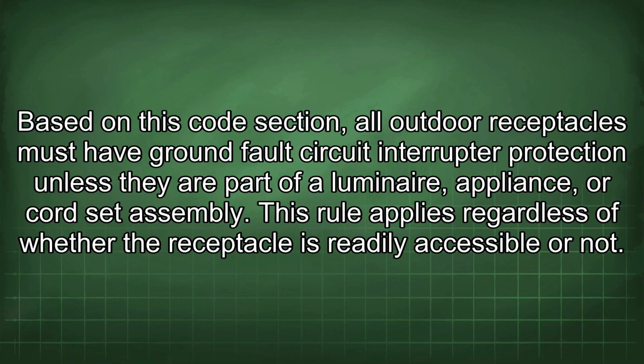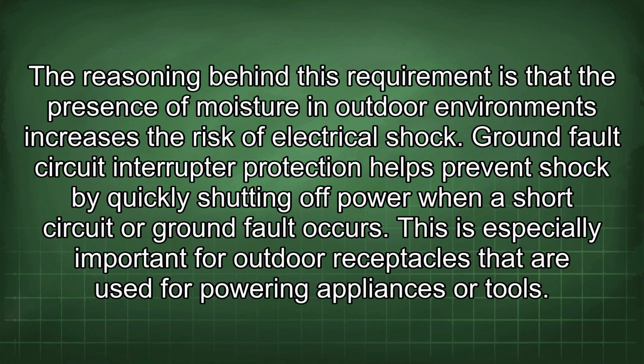This rule applies regardless of whether the receptacle is readily accessible or not. The reasoning behind this requirement is that the presence of moisture in outdoor environments increases the risk of electrical shock. Ground fault circuit interrupter protection helps prevent shock by quickly shutting off power when a short circuit or ground fault occurs. This is especially important for outdoor receptacles that are used for powering appliances or tools.